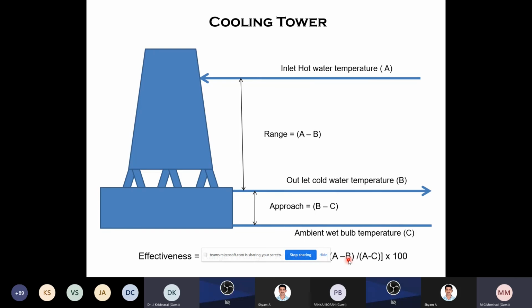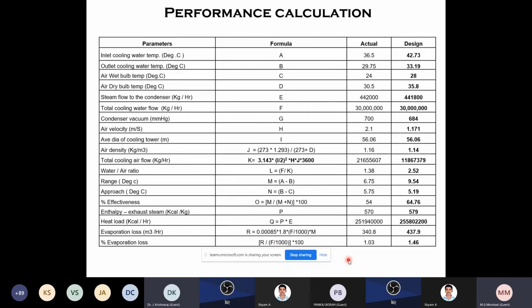But when you go for a performance or energy audit, in such cases you have to go for authentic calculations. There, evaporation loss should be calculated, then effectiveness, then air-water flow, and all other parameters should be calculated during operation. Inlet water and everything else are available, and on the basis of this data you have to work out all the details. It is applicable only for the energy audit.